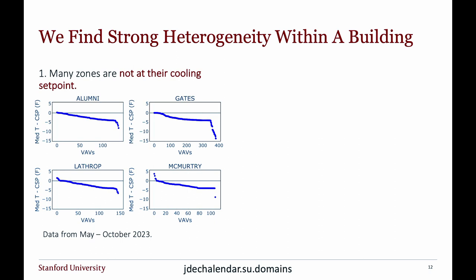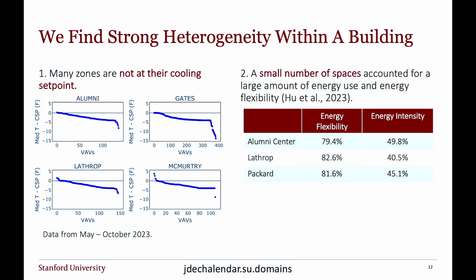What you see is that, depending on the building, it varies, but there are a few zones that are right at their cooling set points. Then there are quite a few somewhere in the middle, and then quite a lot where these lines sort of saturate. Typically a lot of zones are right at their heating set point, which means in the summer the heating is actually turned on to make sure those zones don't get too cold. So that's a first finding.